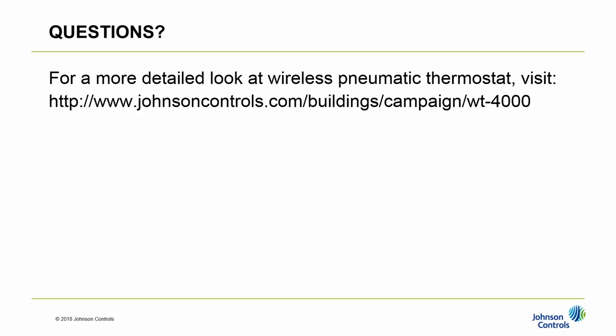Okay, great, thank you. So if someone's using an occupancy sensor on that network, is the occupancy sensor powered from the stat itself, or is there an external source when using batteries? You will require an external power source for that motion sensor, depending on what it is, but you do not need to pull power from the WT4000 for that. All the WT4000 does is accept a dry contact—basically an open-closed signal—to dictate whether it's occupied or unoccupied.